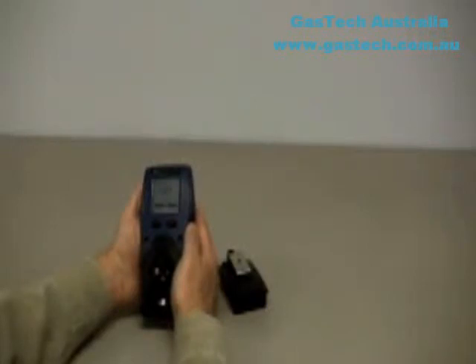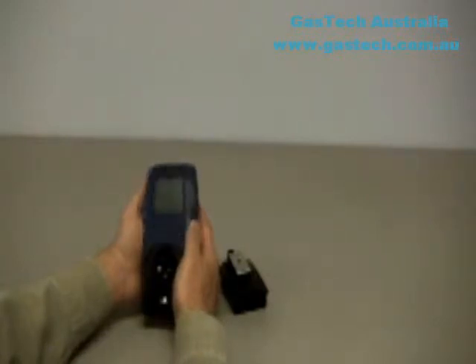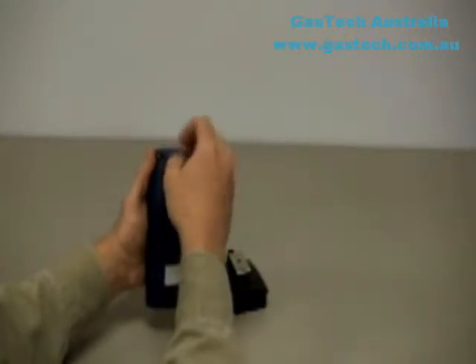The PHD6's batteries are housed in easily removed battery packs. The rechargeable lithium-ion battery packs and alkaline battery packs can be used interchangeably. The instrument automatically determines which type of battery pack is installed. Low battery alarms warn when battery voltage is too low for safe operation.